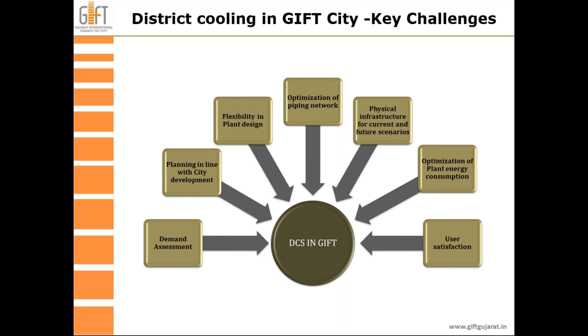In GIFT City, for the 180,000 ton requirement, in the planning we divided it into 3 different plants of 60,000 ton each, located in 3 different locations of the city, such that we have an optimum network of piping. These 3 plants are interconnected with each other, so if any plant goes down due to mechanical or electrical reasons, we will have redundancy with the help of the remaining 2 plants, and the area served by that plant will be served by the other 2.